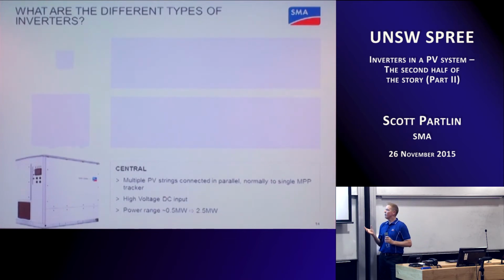And then the last main type of inverter is what within the industry we call a central inverter. Now they're designed as very large inverters, so power ranges in the 0.5 up to 2.5 megawatts at the moment. But similar to the development of wind turbines over the past 10 years, they keep getting bigger each year, and they keep taking higher and higher voltage inputs. So whereas a microinverter might stop at, say, 50 or 60 volts DC input, a string inverter might stop at 1,000 volts DC input. Central inverters are now pushing even higher, up to 1,500 volts DC input, to allow larger strings, to allow more power and reduction of components on the PV plant site. And they can be installed, as with string inverters and microinverters, one at an individual site or multiple units at a single site.